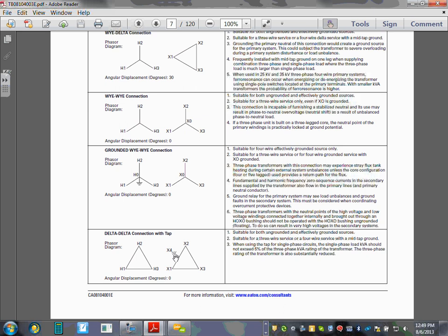They rarely give you a delta center tap. Okay. They give you 2 transformers, 3 transformers as service. Sometimes, yeah. Absolutely. And that leg here, the X1, has to be labeled as orange. It's the high leg. You cannot connect anything between that leg and the neutral by code.